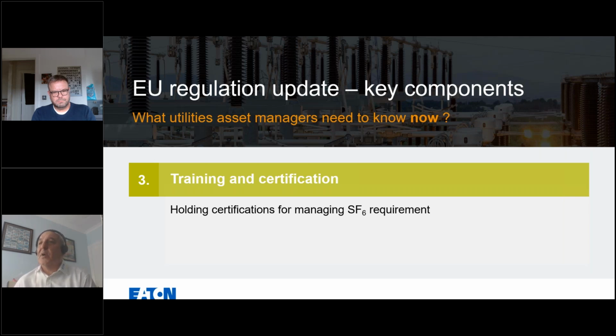Organisations may be required to hold certifications demonstrating compliance with best practices for managing SF6, including its use, recovery, and disposal. At end of life of installed equipment, the SF6 gas needs to be removed. Some systems also require the gas to be topped up, particularly on older products. This is part of the total cost of ownership that we should take into account.